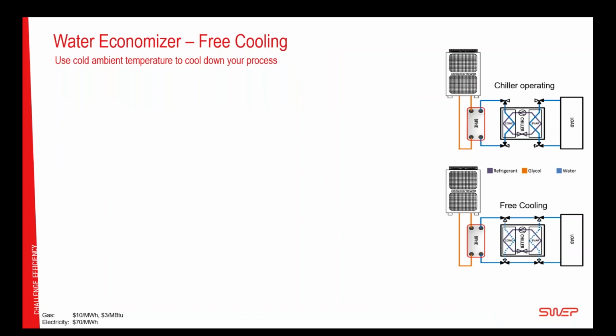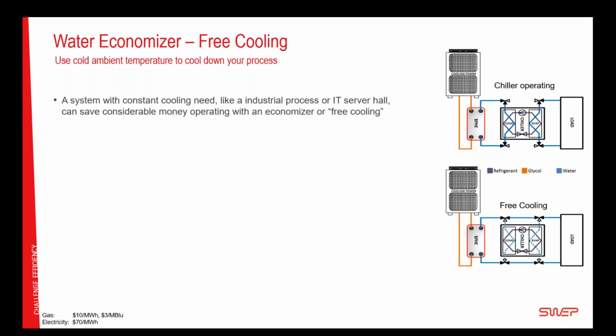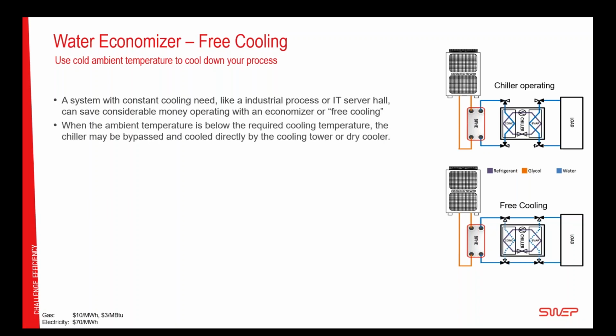So let's go to the free cooling, the way we looked before. The baseline for free cooling is that you have a process or a load side that is needing cooling all year around. An industrial process or an IT server hall, data cooling. If this system is in a climate where it can be cool during parts of the year, there's a significant savings potential here. So what it means is that when the ambient temperature is below what the load side is requiring, the mechanical cooler, the compressors, and everything that consumes energy that we saw before can be turned off, and the cooling can be partly or completely handled by the outside cooling tower or dry cooler.